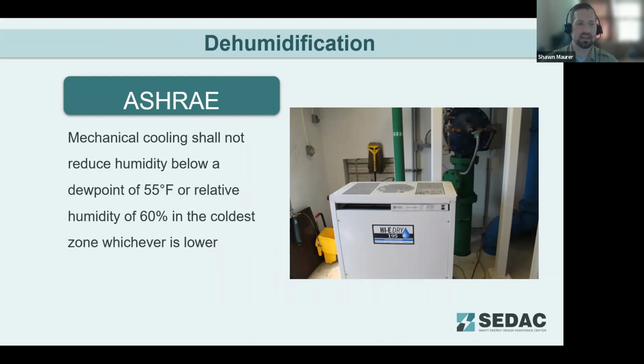For dehumidification, ASHRAE has a requirement for mechanical cooling that shall not allow humidity to reduce below a dew point of 55 degrees or a relative humidity of 60% in the coldest zone of a building. The main thing we're looking at here is condensation control and also wintertime humidity control, and not trying to run the system so much that it dries out the building.